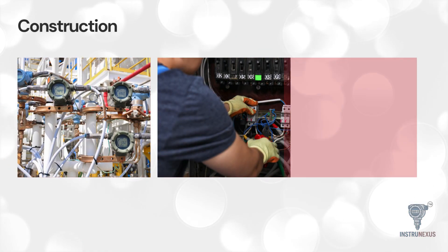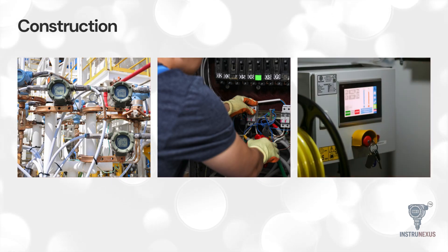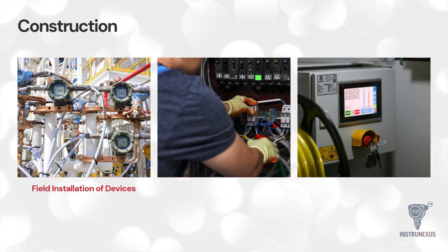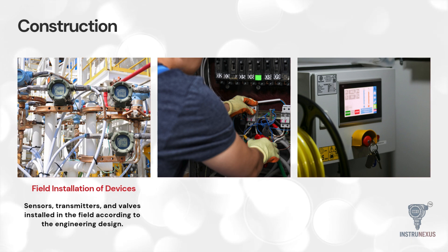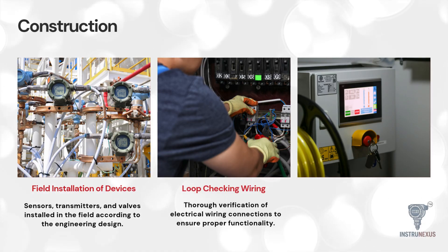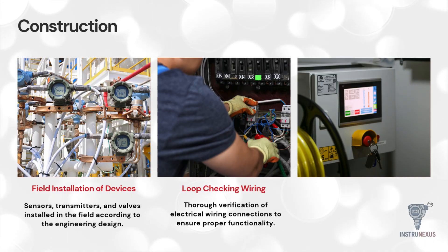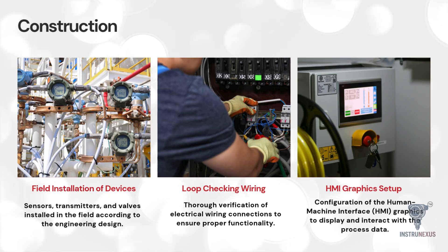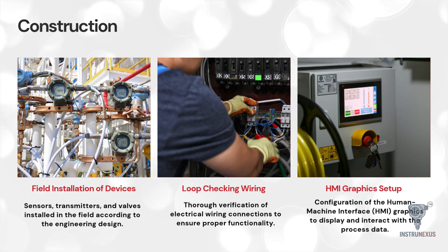While the code is being tested, the physical world is being built. This is the construction phase. Field installation of devices takes place, where sensors, transmitters and valves are mounted according to the design. A crucial step here is loop checking — electricians and technicians verify the wiring from the field device all the way to the control room to ensure continuity and proper polarity. Simultaneously, the HMI graphics setup is finalised. The human-machine interface is configured so that operators can visualise the process data and see the status of the interlocks defined in our matrix.